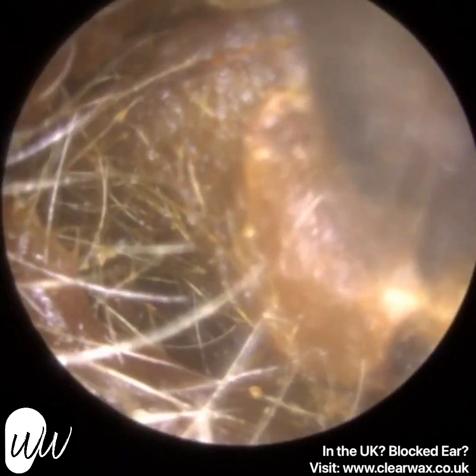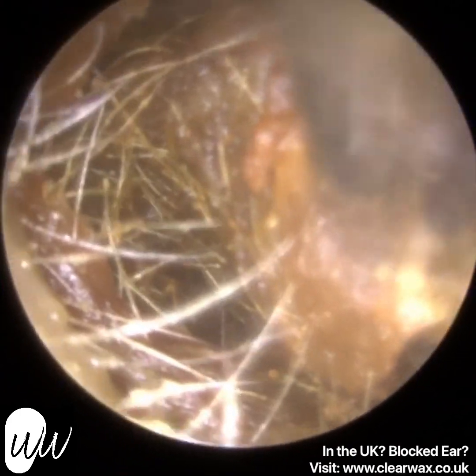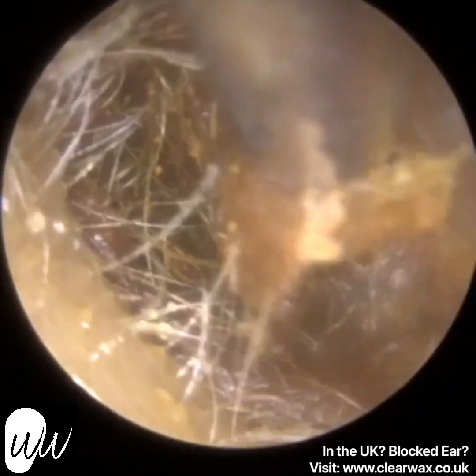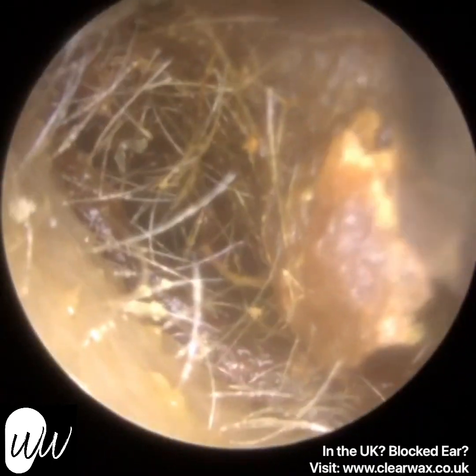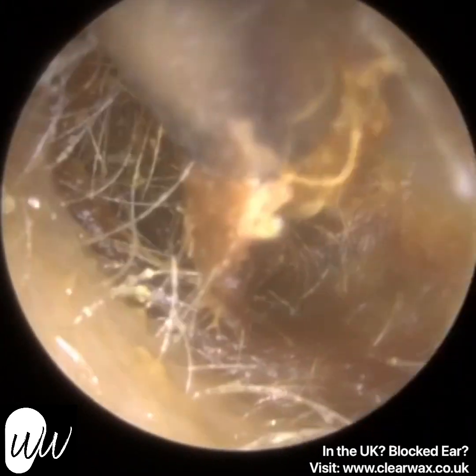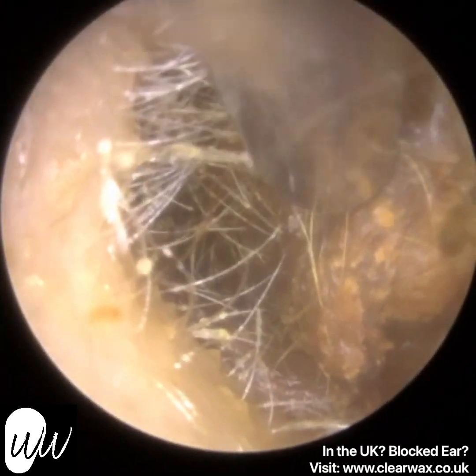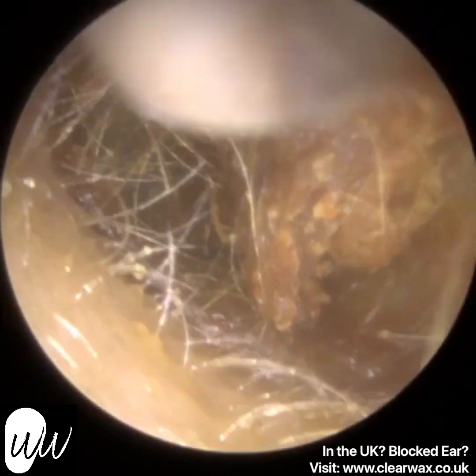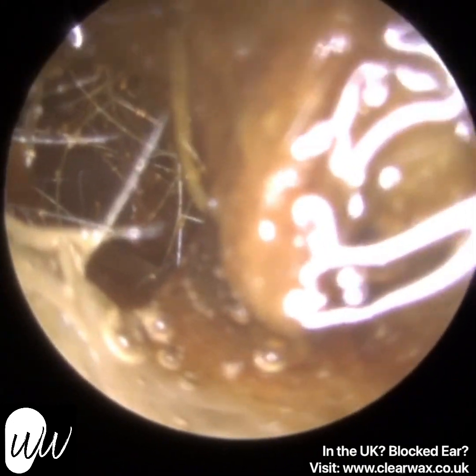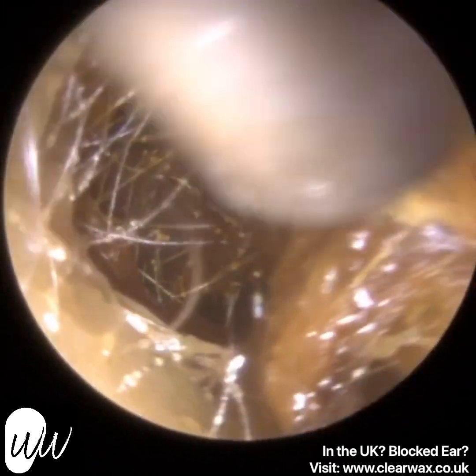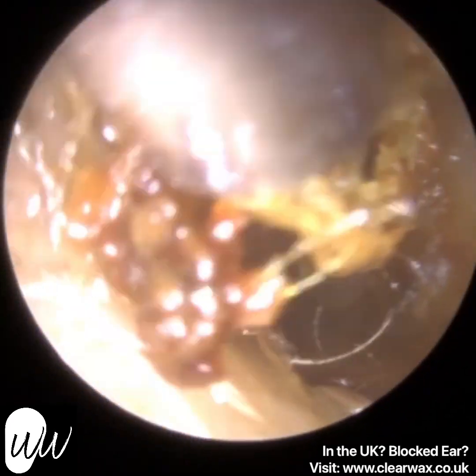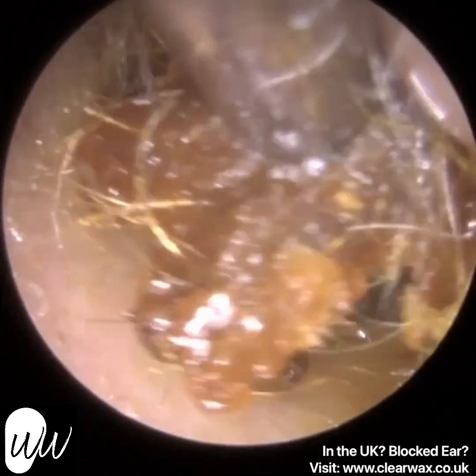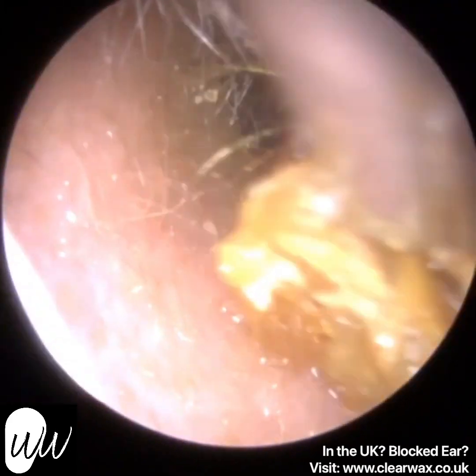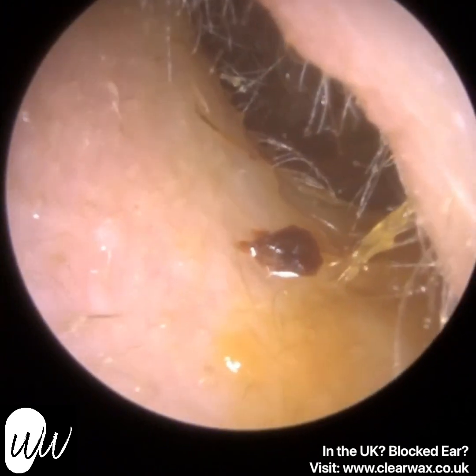That makes it a bit more difficult to perform the procedure because the diameter of the endoscope itself is 2.7 millimeters. The suction probe that I'm using, the Zollner suction probe, is around 2.2. So already we're at 4.9 millimeters. And as I said, the average ear canal at this portion is around 5 to 7 millimeters wide, and the entrance is almost completely collapsed. Without stretching the ear, the instruments wouldn't be able to be inserted in the ear. So we're using the endoscope to stretch the cartilage to the right, at the entrance of the ear canal, and then using the endoscope as a doorstop. We're stretching the ear with the endoscope and then positioning it, lodging it almost like a doorstop to keep the entrance ajar, which then allows me to insert the instrument of choice.